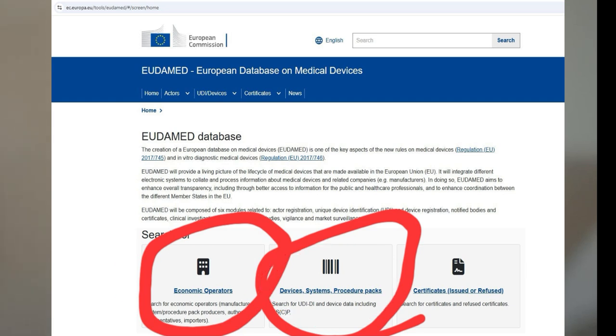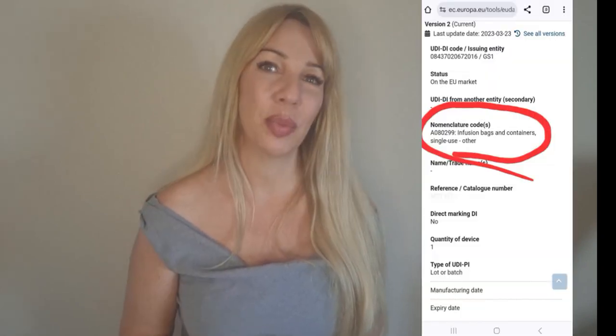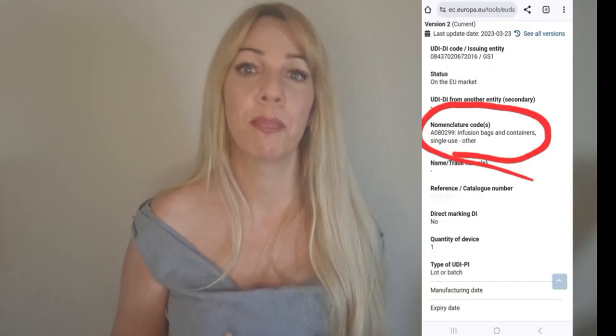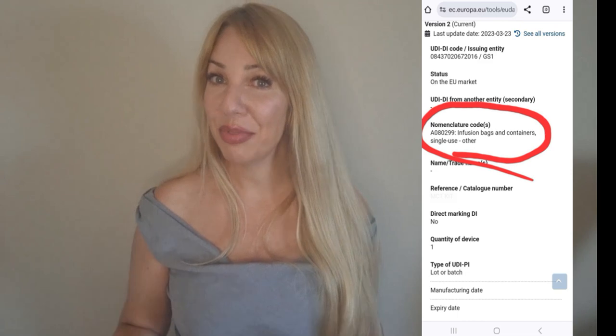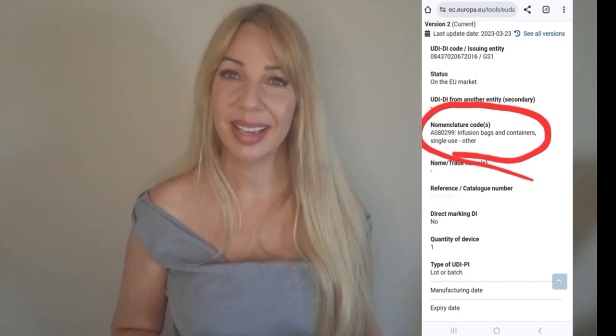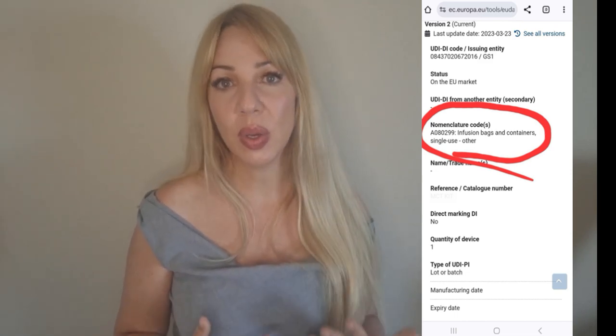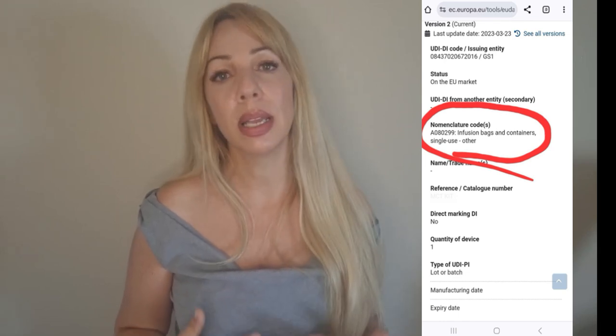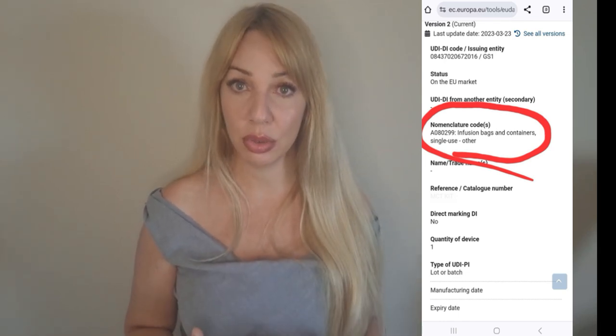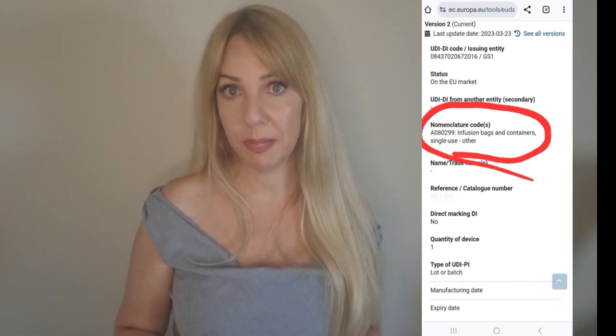But here is a tip. You need to be very precise with the company name. Even minor differences in spelling can result in no matches. Let's assume you do find both the manufacturer and the specific device. What comes next? Look at the nomenclature code and the device description. If you see something like infusion bags and container single use, this is a clear indication that you're looking at a storage device, typically intended to contain infusion solutions, blood or other body fluids. That does not qualify it as an injectable device.